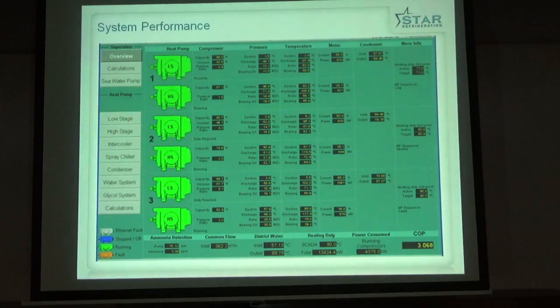A full view of the SCADA, you can see all three systems running. The first is heating the water to about 70 degrees, the second one to about 80 degrees, and the third to about 90 degrees. So they heat the water in series because that's a slightly more efficient way of doing things. And another shot here again, in this case 13.4 megawatts, a COP of 3.068.